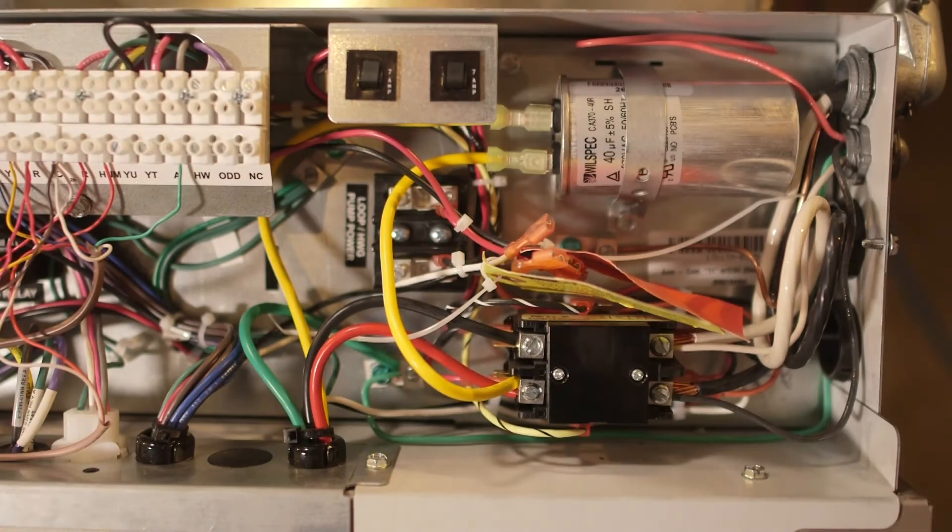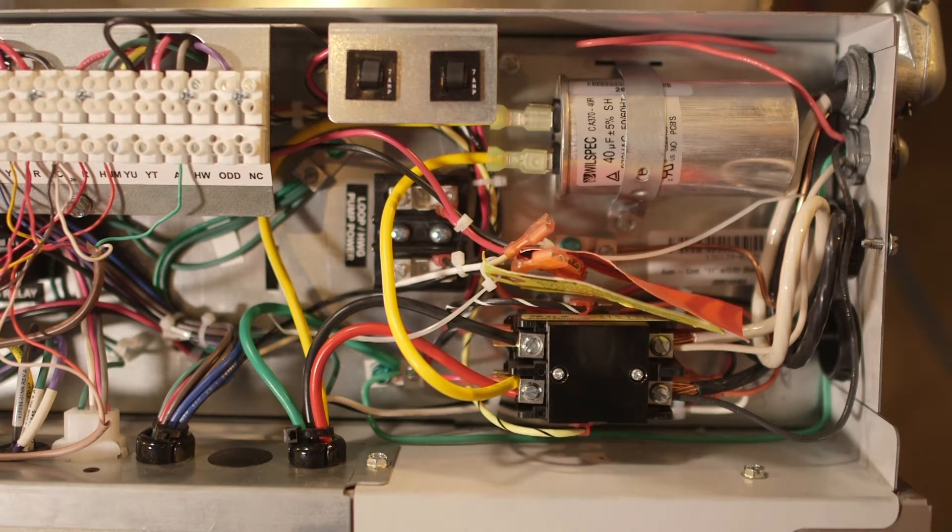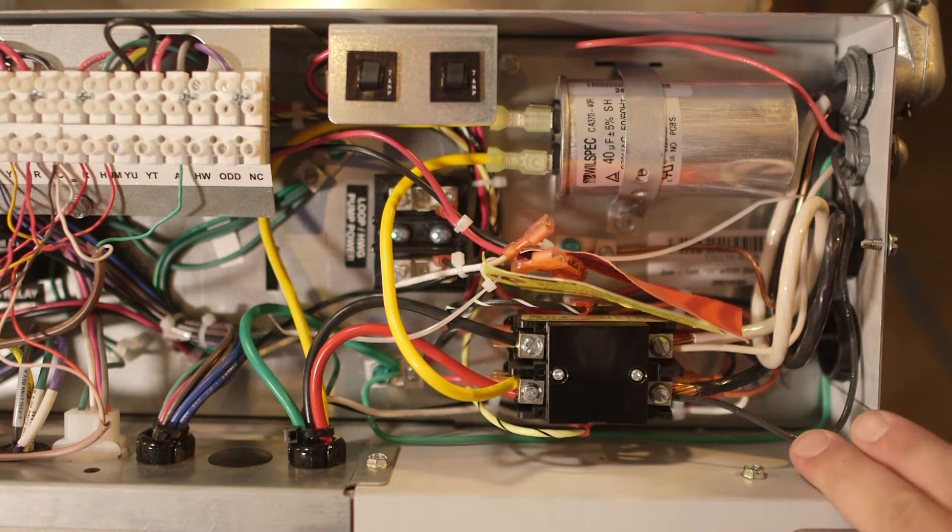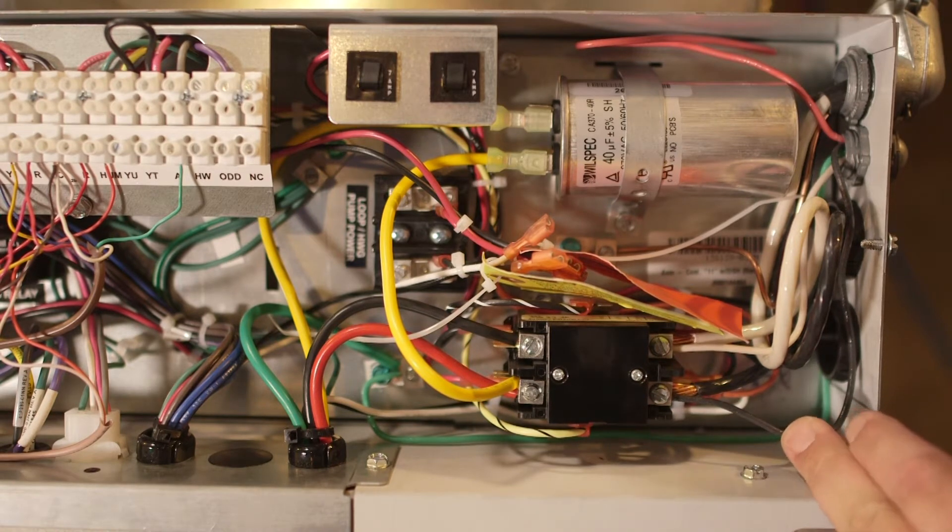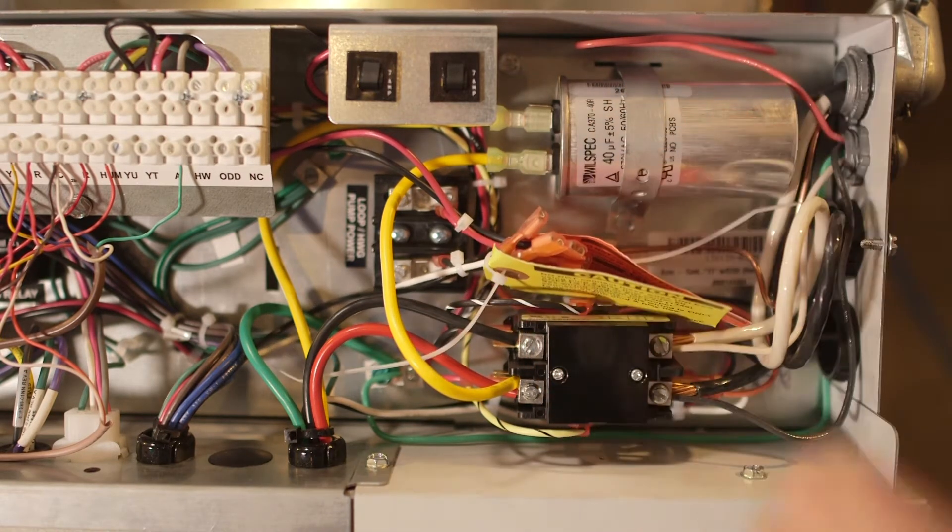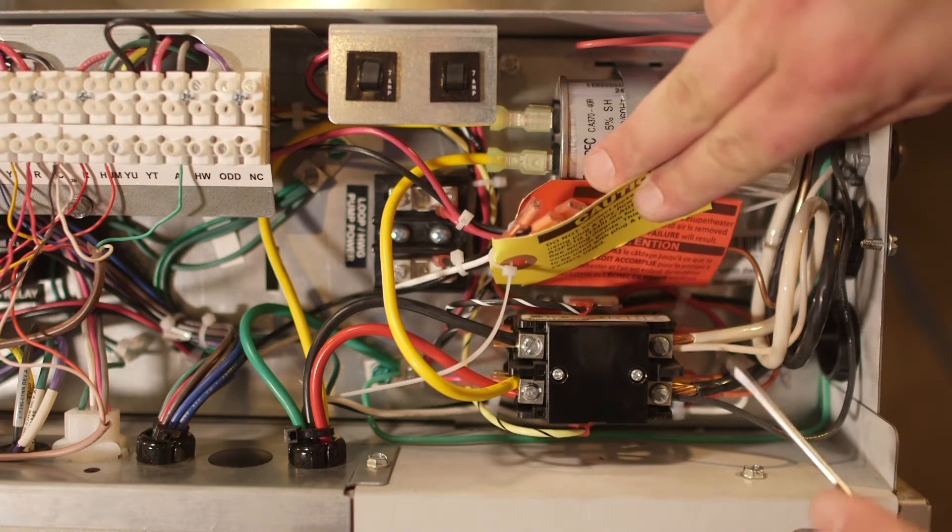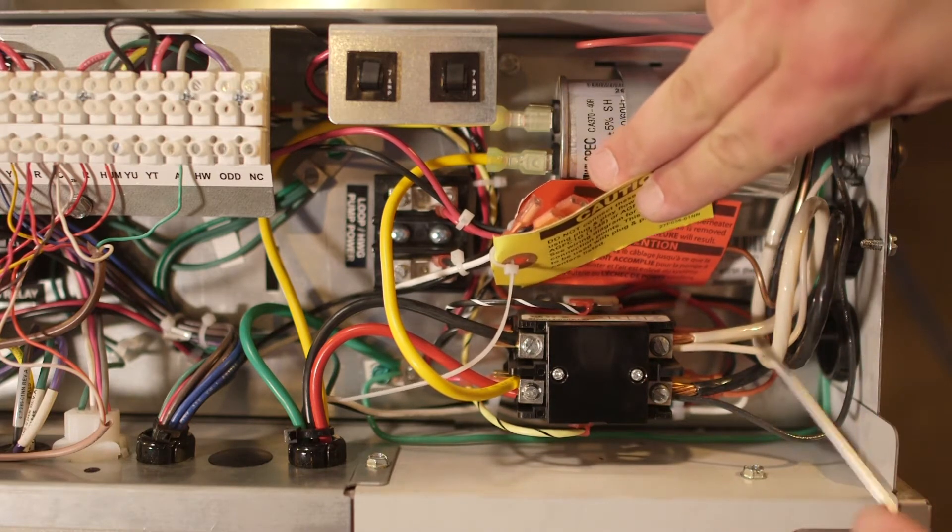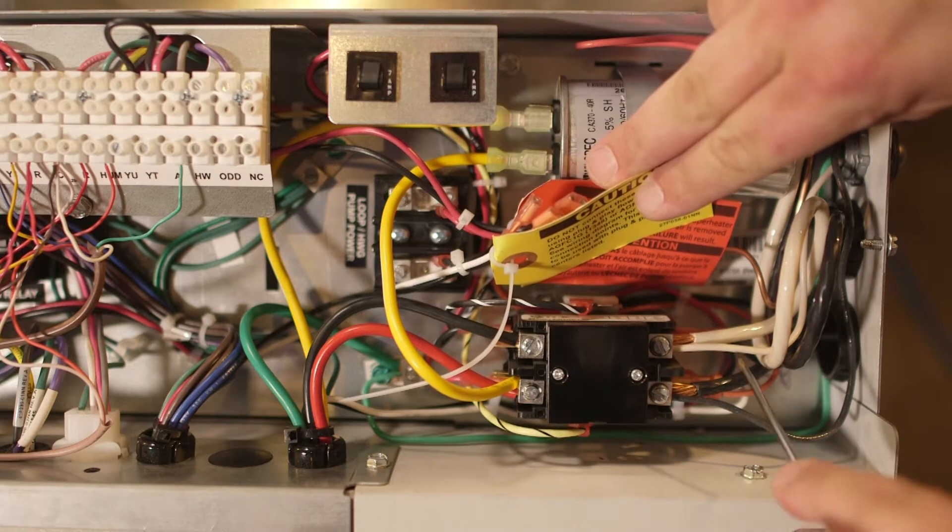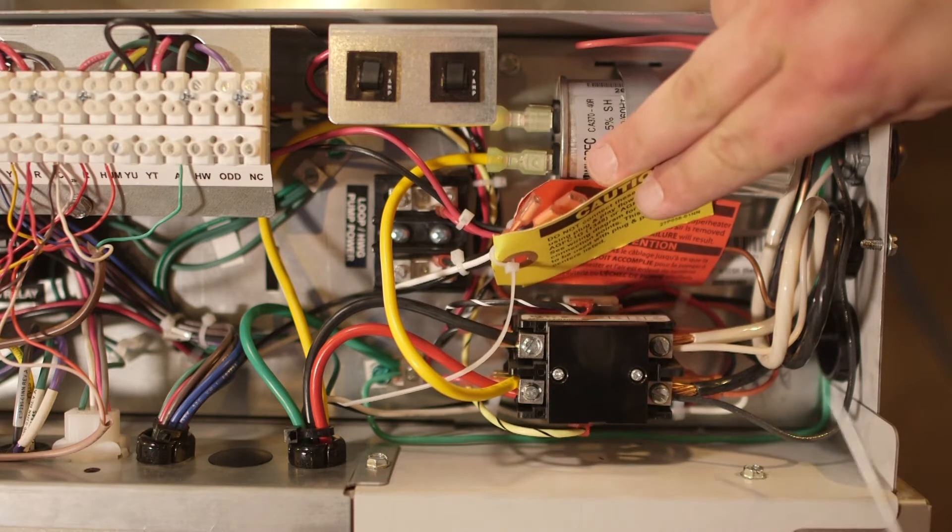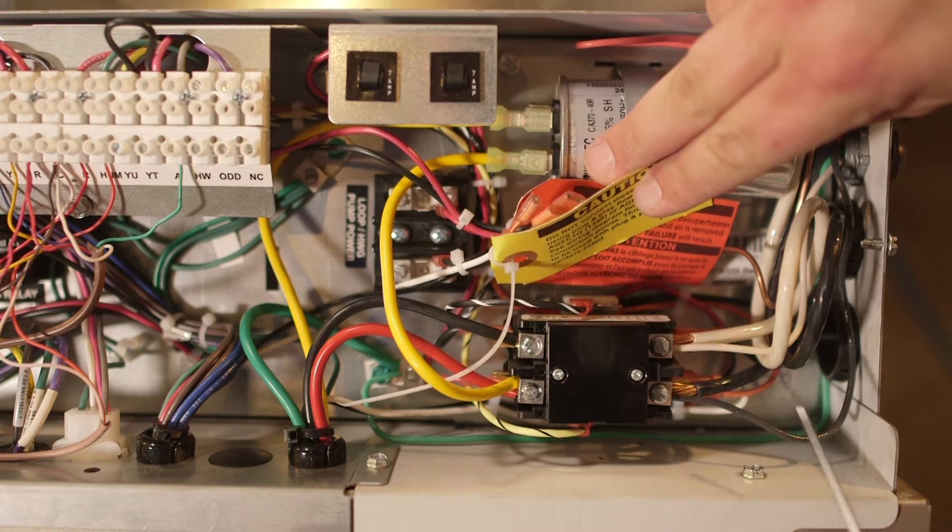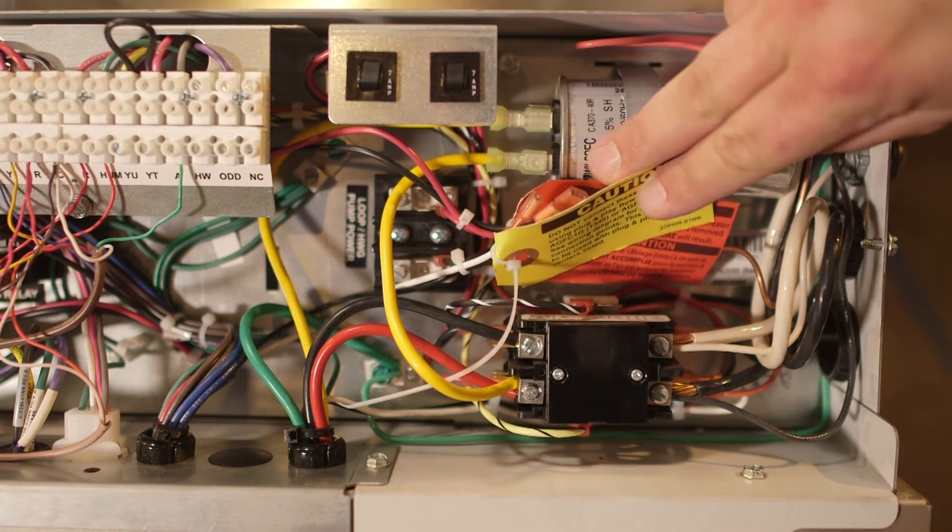Alright guys, so when it comes to the high voltage side of the variable speed flow center, if you do have a single pump variable speed flow center, your high voltage will land just like we have on this unit, right in with the contactor. You can see here we've got our high voltage coming in from our breaker panel, and we've got the smaller green field here that runs over to power our variable speed pump.